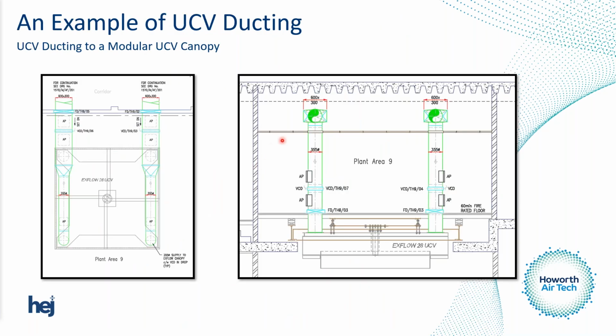Another way to do it is to bring cylindrical duct straight to the back of the fan. You can see here, this was a project I worked on a long time ago. We have the ductwork that's sort of shot across the top of the plant room, and then it dropped equally. Symmetry is the key at each corner of the UCV. You can see we've got a VCD access panel, so you can get in and check that, and we could drill, take our traverses. We could even balance it on pressure. The system was that symmetrical.